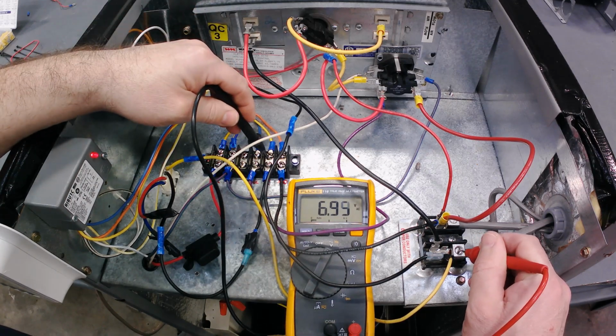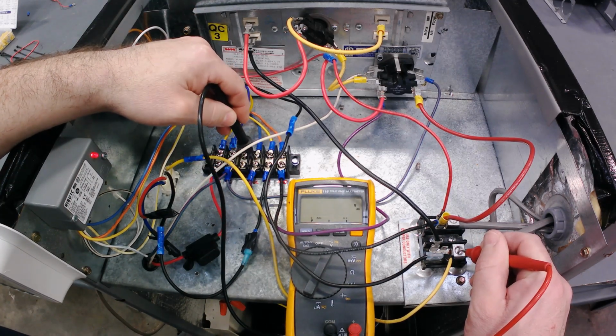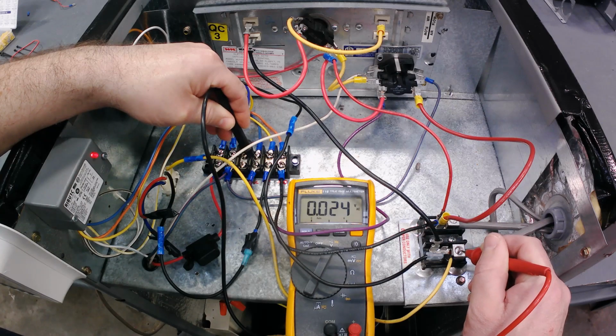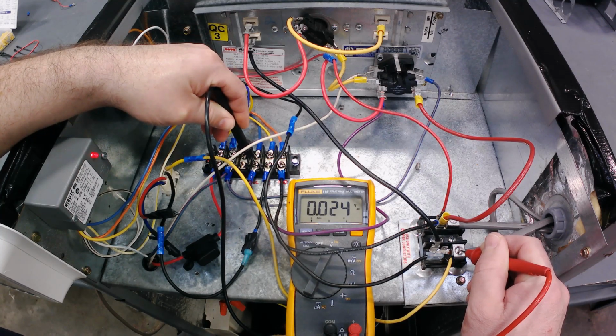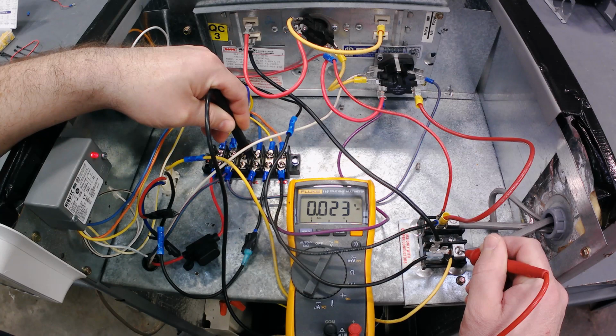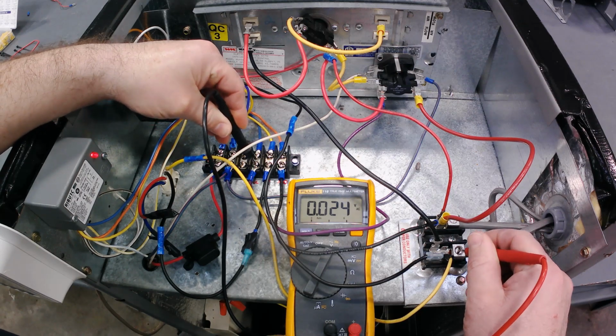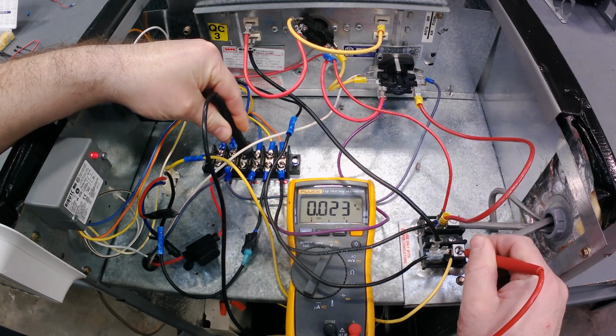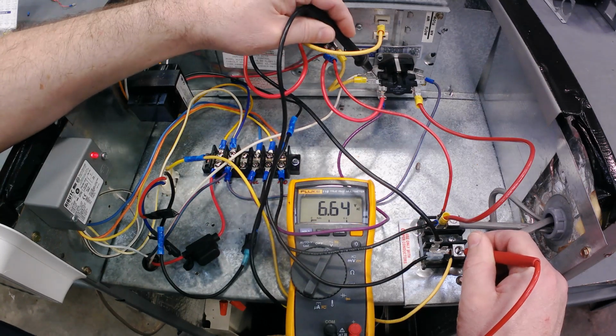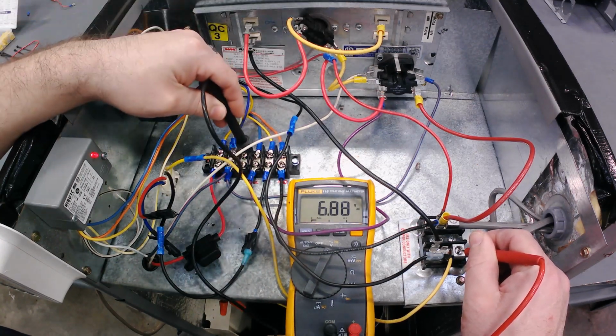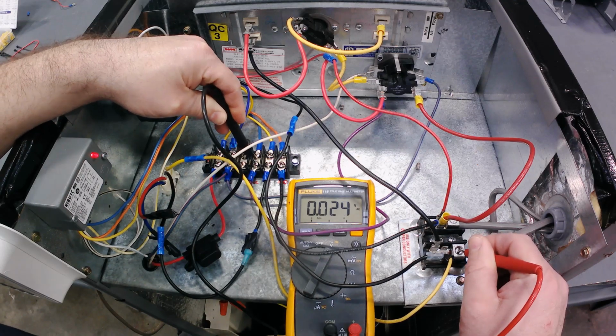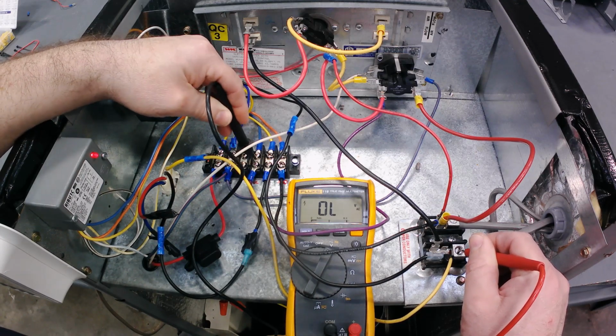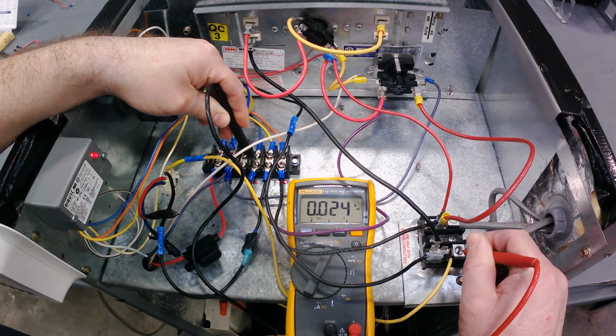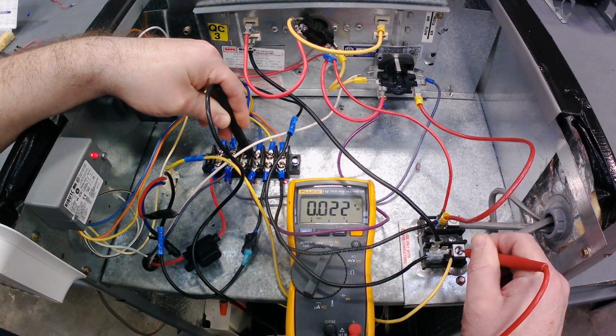But look what happens when I check the other one. 0. Why? Because this leg, this normally closed leg over here, has no power on it right now. There's voltage there, but the way that we're reading it is we're on the same side of power, because we're backfeeding actually through this heat sequencer, and it's checking the L2 side. So L2 to L2, if I'm checking in this situation, is 0. No difference. Doesn't mean no power, means no difference.